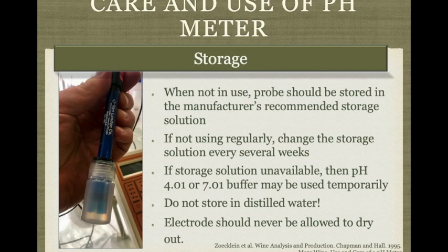It's important to store these correctly too, as per the manufacturer's recommendations. If you're not using it regularly, you change the storage solution every several weeks. If you find you've run out of storage solution, you can temporarily store it in one of the buffers, but only temporarily. But do not store it in distilled water, and try not to ever let it dry out.